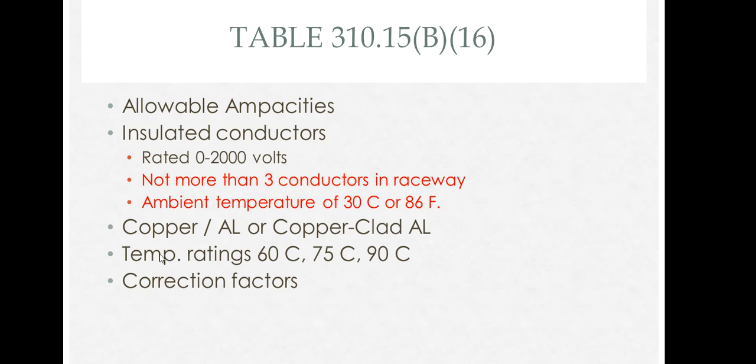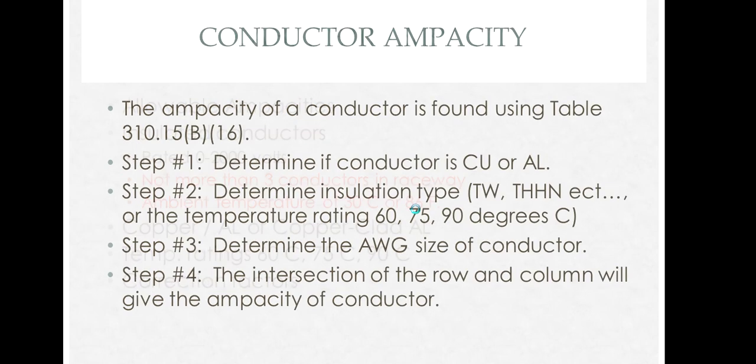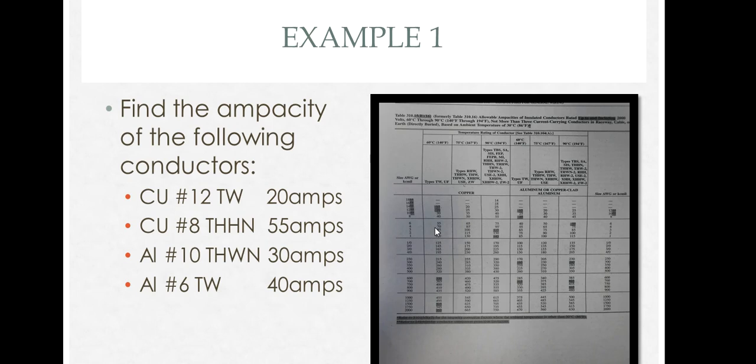This discusses the temperature information about the table. I want to reiterate that there's not more than three current carrying conductors in the raceway, and the temperature was at 86 degrees Fahrenheit. To determine the ampacity, you would take the intersection of the column and the row.